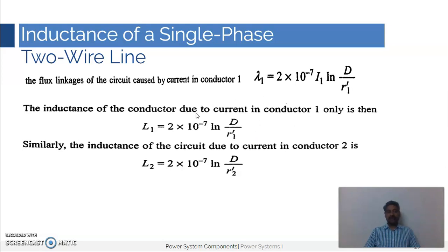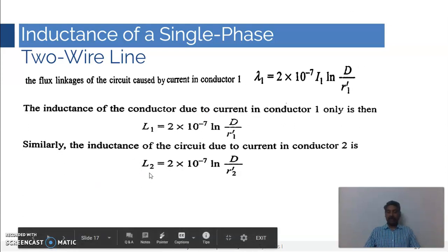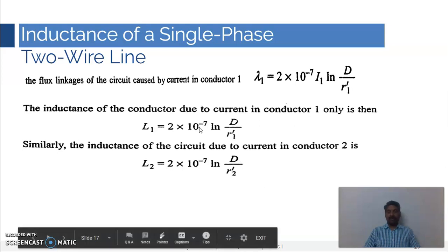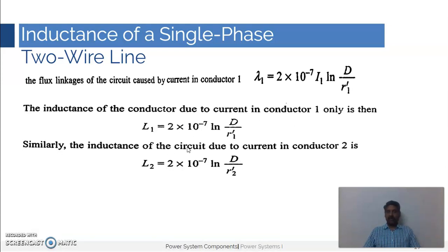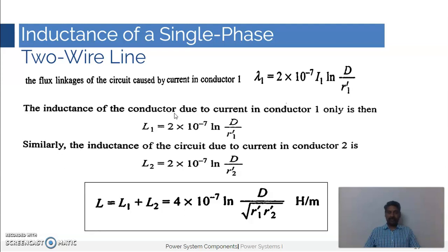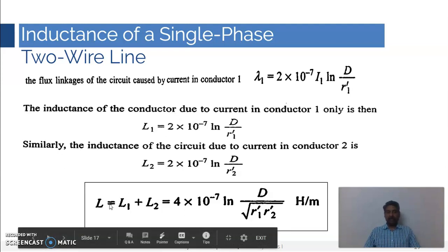The inductance of conductor one is calculated by dividing λ1 by i1, giving L1 = 2 × 10⁻⁷ × ln(d / r1'). In a similar fashion, without considering the flux linkages due to current in conductor one and considering only current in conductor two, you can derive L2 = 2 × 10⁻⁷ × ln(d / r2'). Using the superposition theorem, the total inductance is L = L1 + L2.